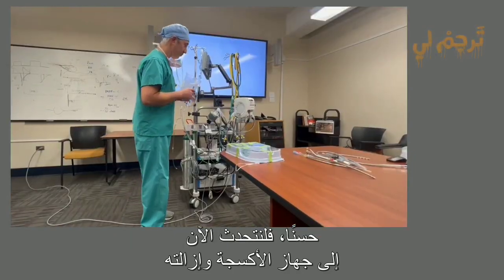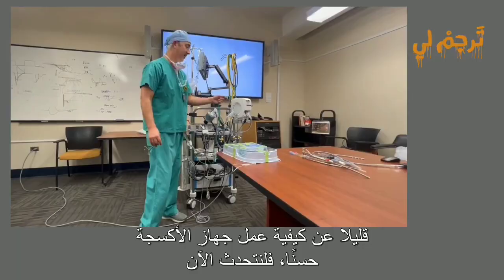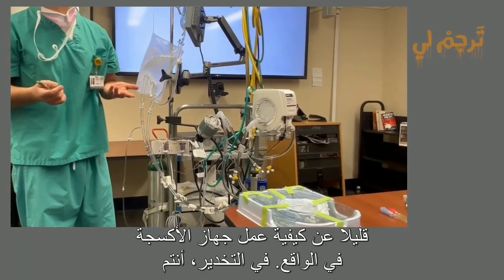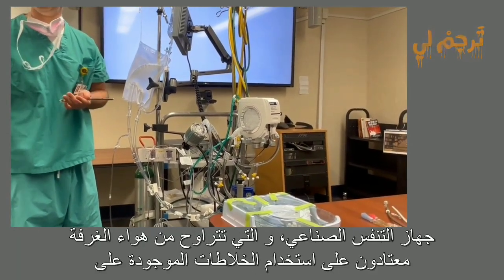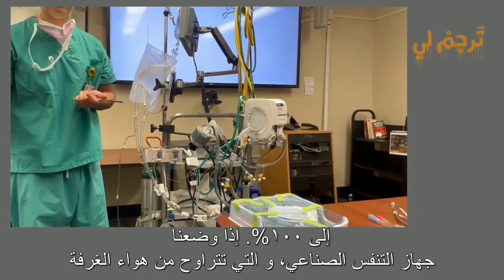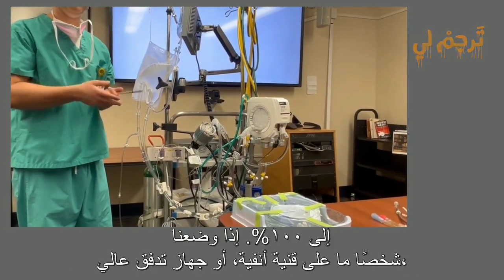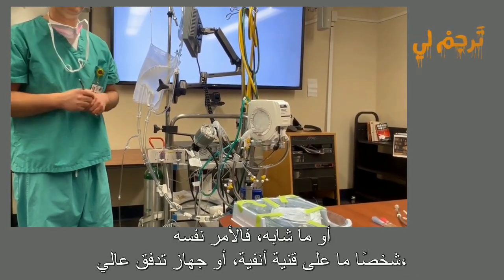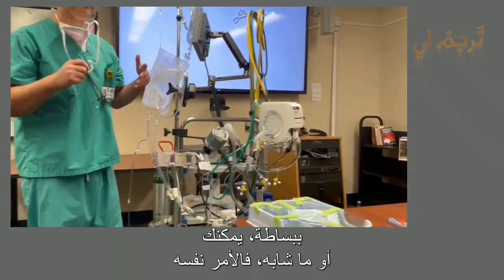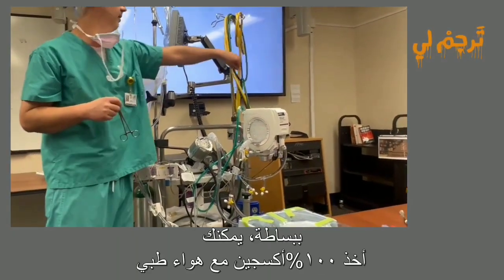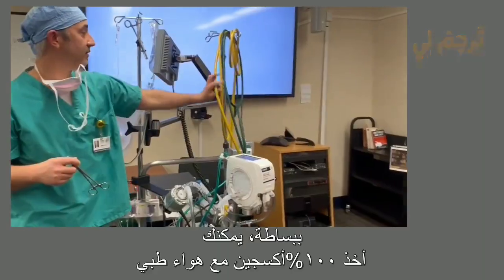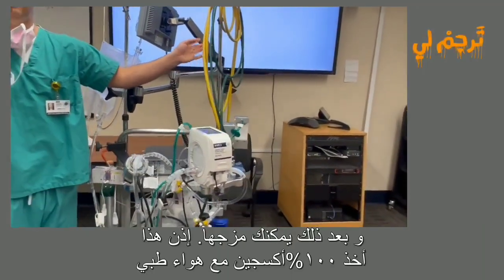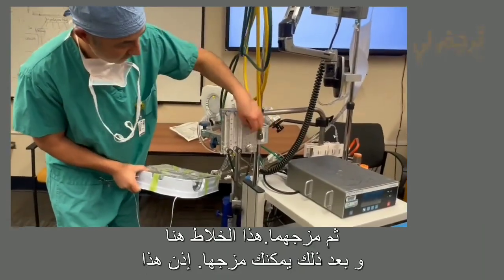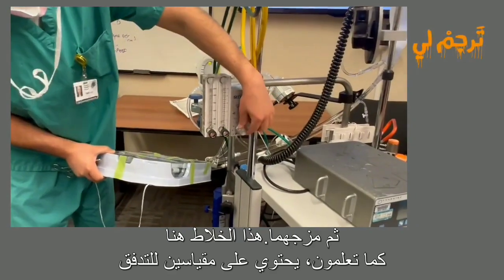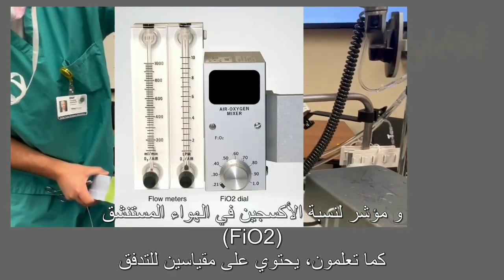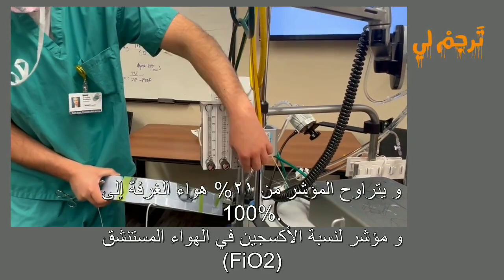All right. So now let's talk a little bit about how the oxygenator actually works. So in anesthesia, you guys are used to blenders on a ventilator, it goes from room air all the way up to 100%. If you put someone on a nasal cannula, high flow or something, same thing. You take 100% oxygen with medical grade air, and then you can mix it. So this blender here, it's got 2 flow meters and then a dial for your FiO2. And the dial goes from room air, 21%, all the way up to 100%.